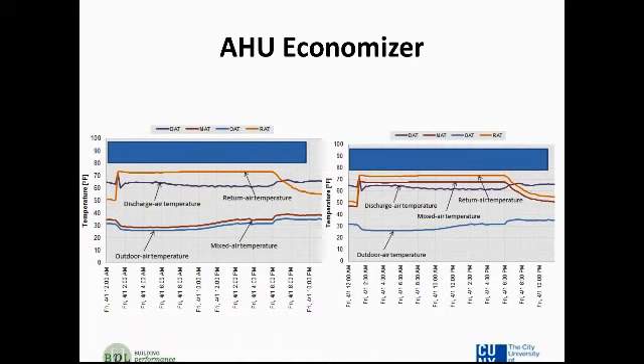Another couple of examples here on the left-hand side. Once again, this is a 24-hour period, and I want you to keep in mind the outdoor air temperature, we know what that is. We've got return air in the orange line running along the top. And then we've got the outdoor air mixing with that return air to make the mixed air. You can see the mixed air temperature on the left-hand side is following the outdoor air temperature very closely. And what that tells you is that most of your mixed air is in fact outdoor air. You're throwing away most of your return air.